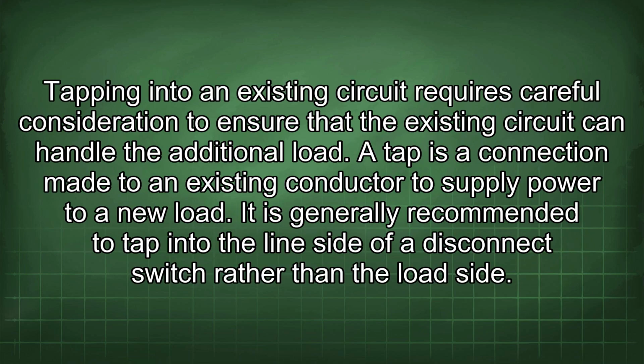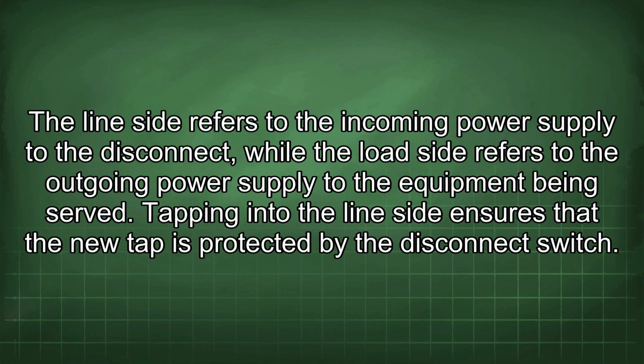Tapping into an existing circuit requires careful consideration to ensure that the existing circuit can handle the additional load. A tap is a connection made to an existing conductor to supply power to a new load. It is generally recommended to tap into the line side of a disconnect switch rather than the load side. The line side refers to the incoming power supply to the disconnect, while the load side refers to the outgoing power supply to the equipment being served.